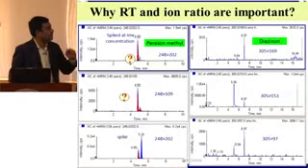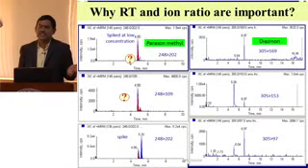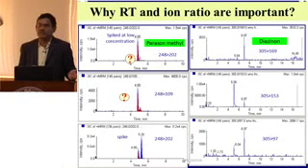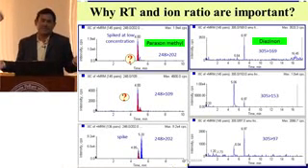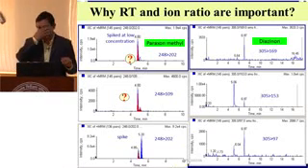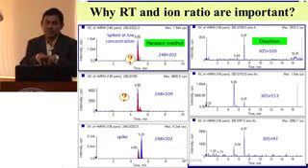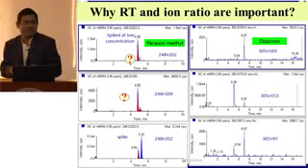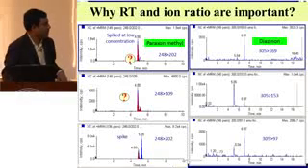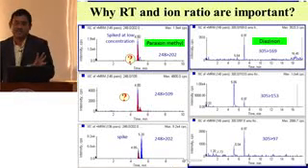Another important thing is that we should not forget about retention time. People have a general tendency that since we have LCMSMS or GCMSMS, we really do not need to bother about RT. But sometimes what happens is that RT could be very close for two co-eluting compounds having similar mass transitions. Under such a situation, it's very difficult to say whether your analytical result is correct or not.